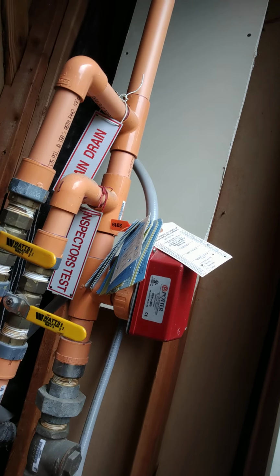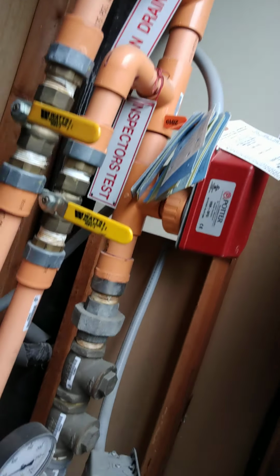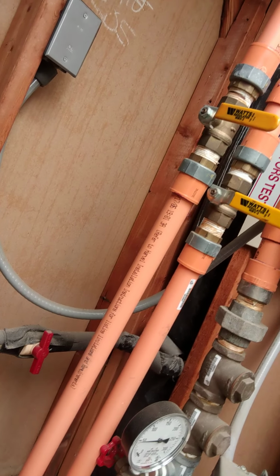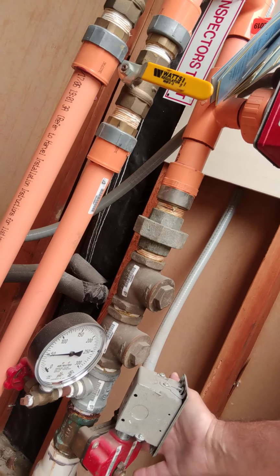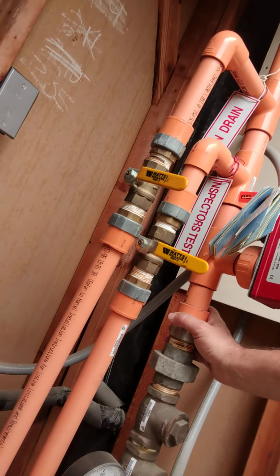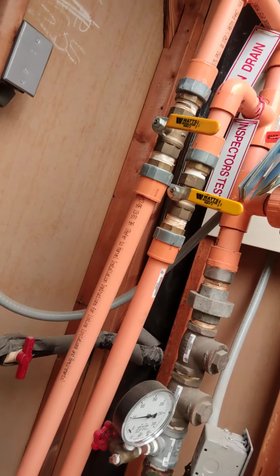If for any reason you ever have to drain down the building, number one, always put your property in test. If you go over here and start tampering with this valve, it's going to send either a tamper signal or maybe a supervisory signal. At a minimum, you'll get a phone call from the monitoring company. Worst case scenario, you could have the fire department show up and they could fine you for that. So if we were going to do some work in this building and needed to drain it down, we would close this off so we can maintain pressure in the sprinklers, and then we could go ahead and do what we needed to do.